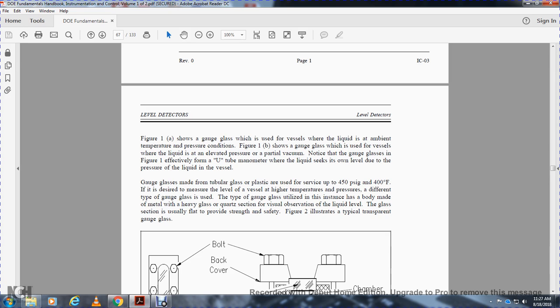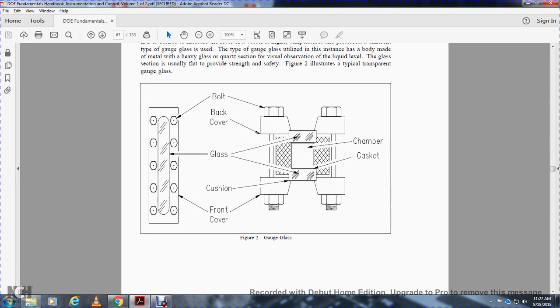Gauge glass is made with tubular glass or plastic, up to 450 psig and up to 400 degrees Fahrenheit. It is the desired measure for the level of a vessel with high temperature and pressure. There are different types of gauge glass. The typical gauge glass is utilized with a metal body with heavy glass, a quartz section for visual observation of the liquid level, and the glass section is usually flat, providing strength and safety. Figure 2 illustrates the typical transparent gauge glass. It shows the chamber, gasket, the glass, and the bolt, back cover, cushion, and front cover.